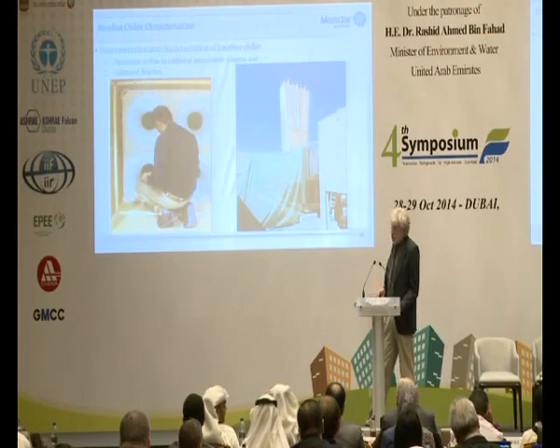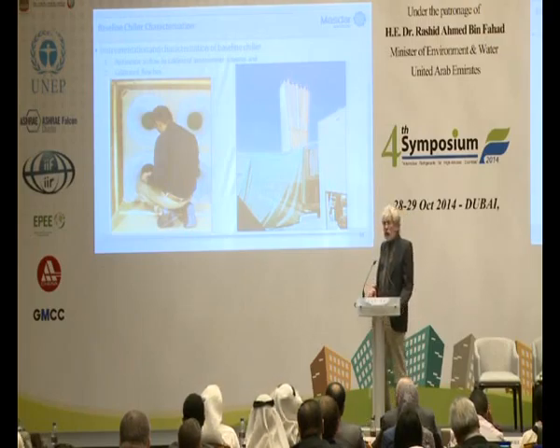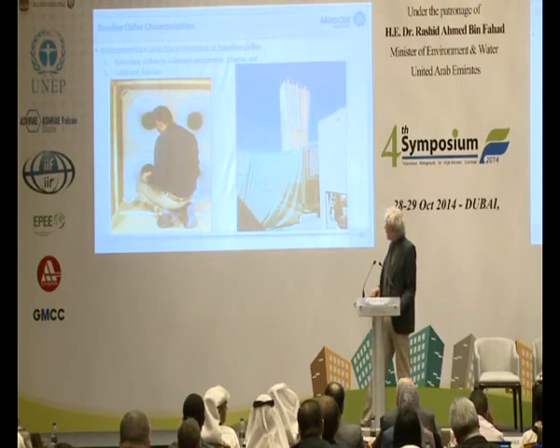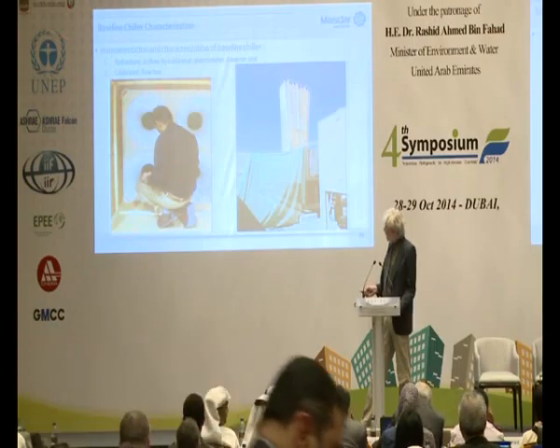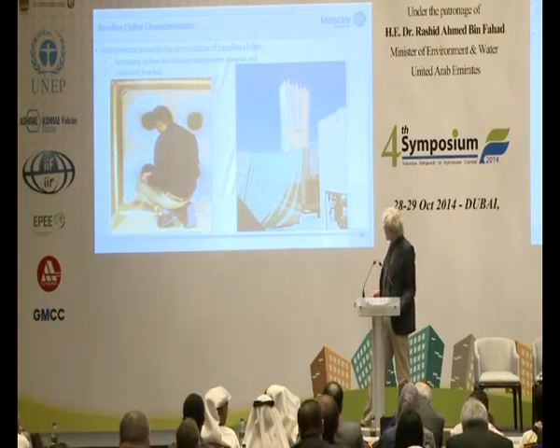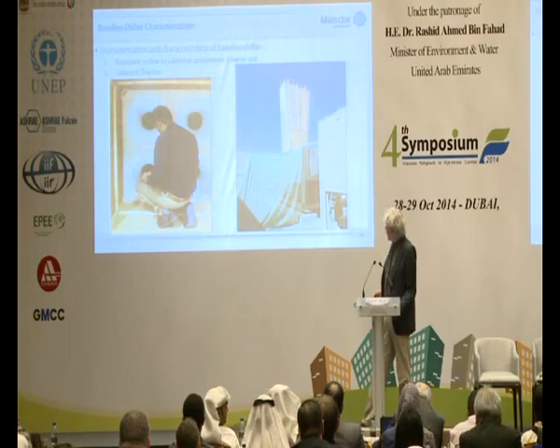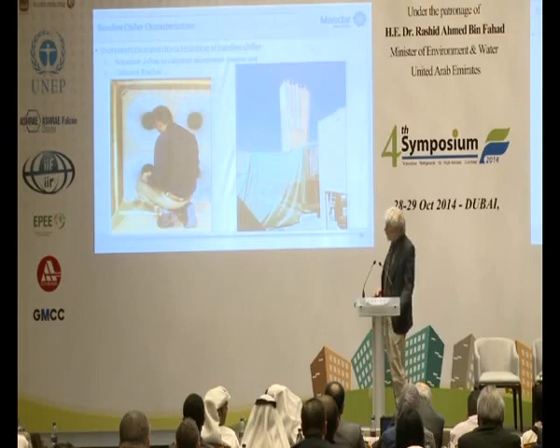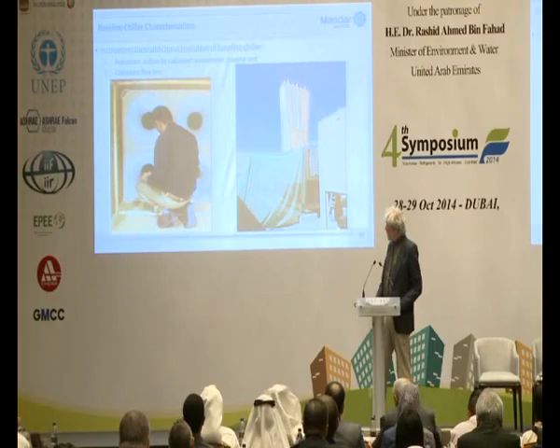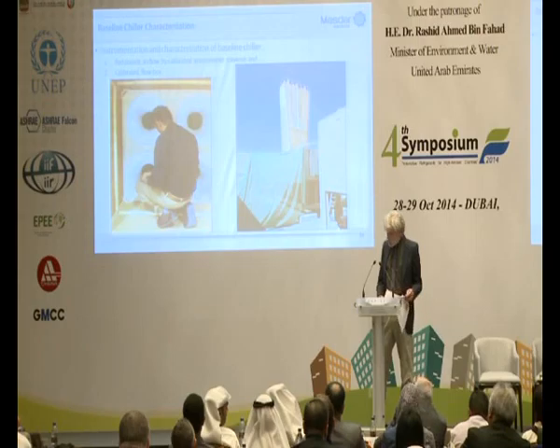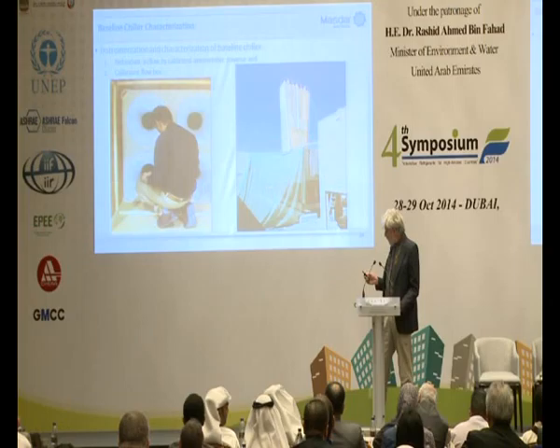And we actually do redundant measurements, so we measure the flow of each condenser fan with this apparatus, which has been calibrated using the ASME nozzle apparatus. And then we also do traverses, and here you see a screen that shields the condenser inlet face from the wind so as not to bias the measurements. And with these two methods, we can get agreement to about 5%. And that helps us to get a heat balance on the whole machine to about 5%.